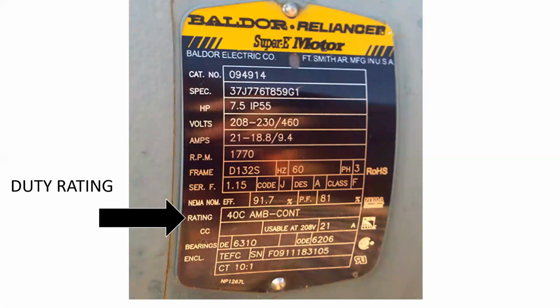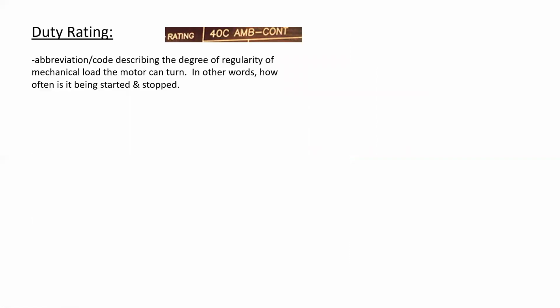Duty rating. This motor has a duty rating that is 40C AMB continuous, or CONT. Now, the duty rating is an abbreviation or code describing the degree of regularity of mechanical load the motor can turn. In other words, how often is it being started and stopped? This particular motor says it is rated for CONT, and that abbreviation is in reference to the word continuous. What it's rated for is continuous running operation. And this is the least taxing of all the different duty ratings that are available for motors. It means it's being turned on and it pretty much just runs for most of the day.